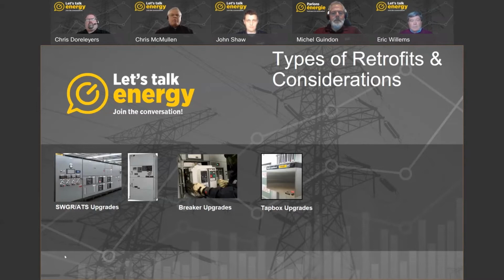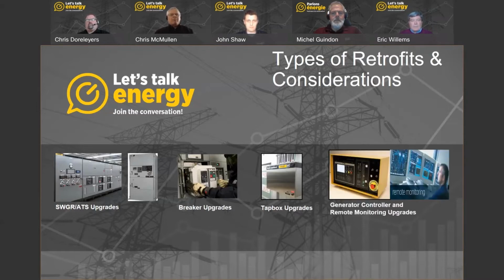Generator controller and remote monitoring upgrades. Onboard generator controllers are typically modular based. Not often can we change out the failed part, but must change out the entire controller. This now affects everything wired to the controller. Duplicate sensors or switches on these engines can now be upgraded to watchdog or active type sensors. Logic in the control negates the need for a switch and a sender to monitor the same condition. An example of this is a customer's insurance for uptime and remote monitoring.